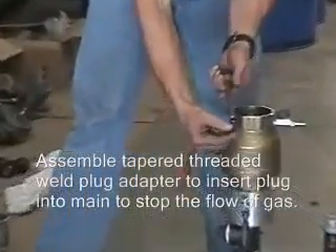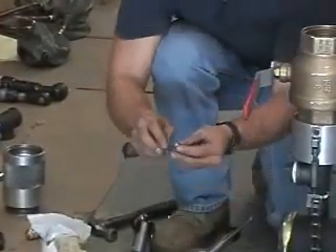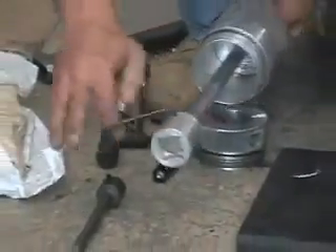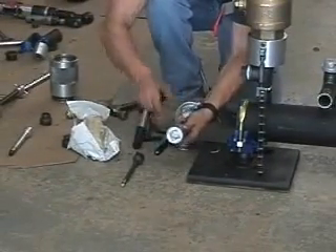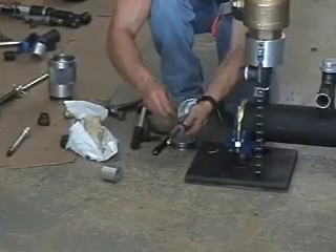Insert the properly sized tapered threaded weld plug into the adapter. Place a small piece of thread seal mastic around the bottom half of the weld plug and press the mastic into the threads with your finger. Remove the plug adapter and fit the tapered threaded weld plug adapter onto the T-handle shaft. Then tighten the set screw using the hex key.